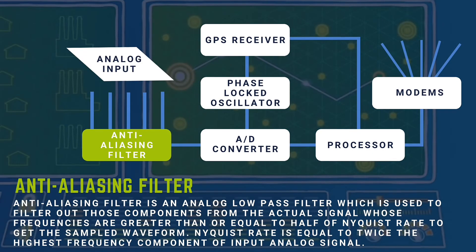Anti-aliasing filter: An anti-aliasing filter is an analog low-pass filter used to filter out signal components whose frequencies are greater than or equal to half the Nyquist rate to get the sampled waveform. The Nyquist rate is equal to twice the highest frequency component of the input analog signal. If anti-aliasing filters are not used, error will be introduced in the estimated phasor.